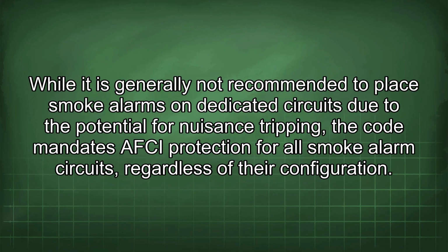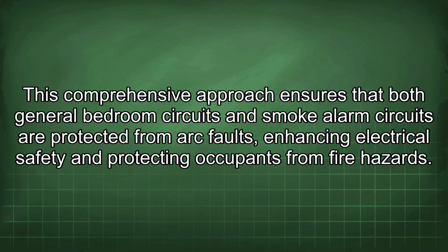While it is generally not recommended to place smoke alarms on dedicated circuits due to the potential for nuisance tripping, the code mandates AFCI protection for all smoke alarm circuits, regardless of the configuration. This comprehensive approach ensures that both general bedroom circuits and smoke alarm circuits are protected from arc faults, enhancing electrical safety and protecting occupants from fire hazards.